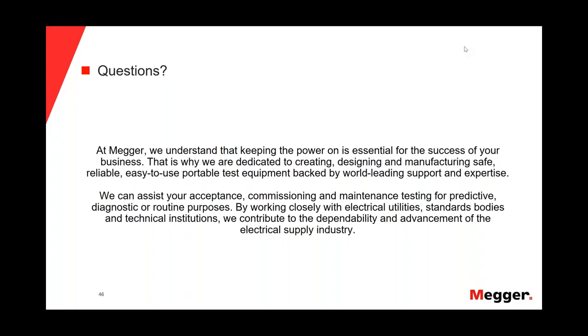Well, keep in mind that we will apply the voltage for the PD test between the center conductor and the concentric. So we are looking mainly for issues in the insulation of the cable or the splices and the terminations. So problems in the jacket of the cable will be quite difficult to detect with partial discharge. At least that damage will be related with other damage.